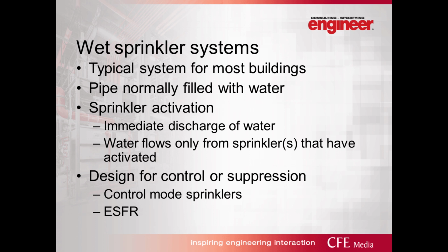So wet sprinkler systems are the most typical that you'll find in commercial buildings, and if you're lucky enough to have one in your residential building, in residential buildings as well. This is a simple system. The branch piping and all the piping for the system are filled with water normally.